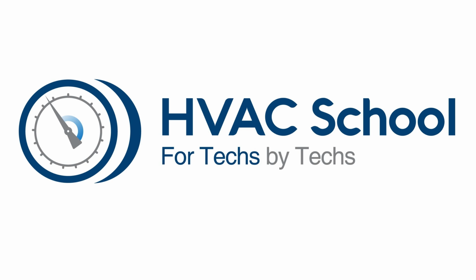So they have a little bit of give in them, so when they try to compress that vapor or liquid, it's not going to just explode. That's a common thing even nowadays with scroll compressors, where they can handle a certain amount of liquid because of that axial and radial compliance - the actual compressor has the ability to flex open a little bit so that some liquid can pass through.